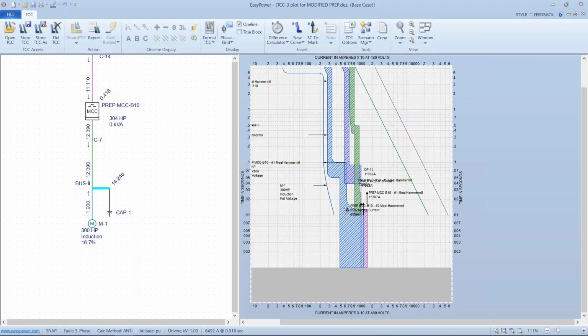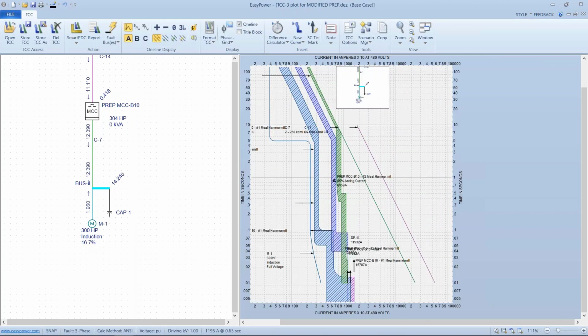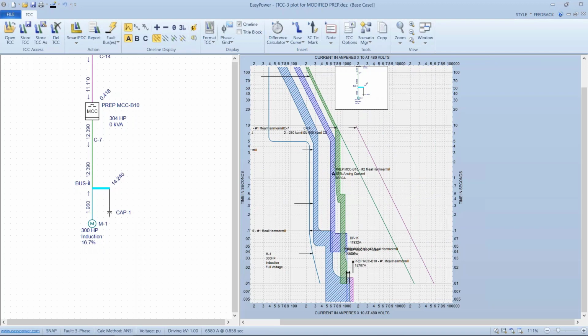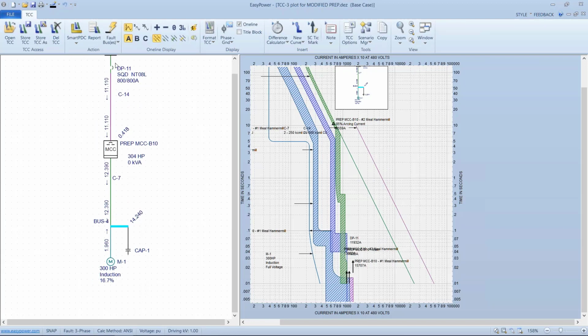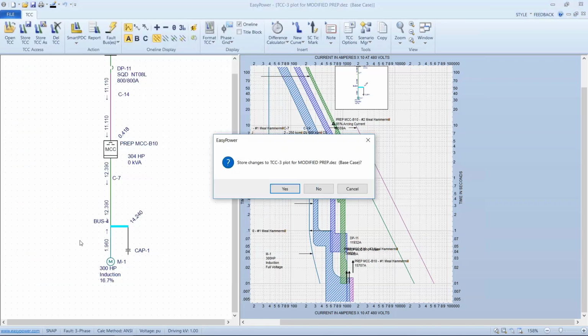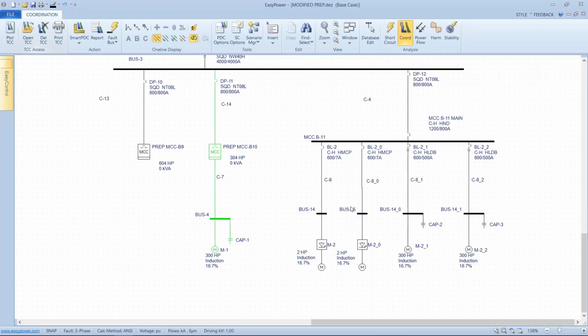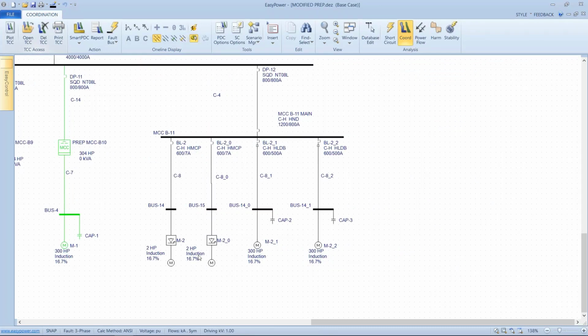And we can see here, at least for arcing current, we have coordination because it'll trip my downstream breaker first, then the main breaker, and then several seconds later, it'll trip the upstream breaker that we have indicated for DP11. So this gives us the ability then to coordinate with the downstream load, and I want to compare that against the similar philosophy of doing a discrete implementation.